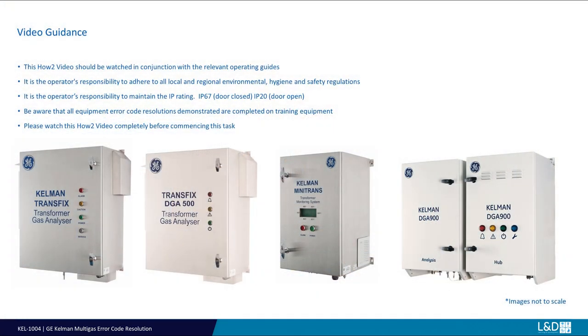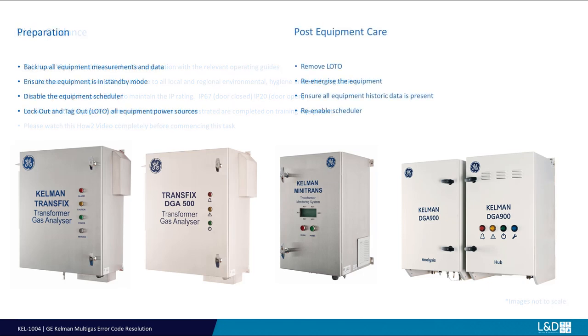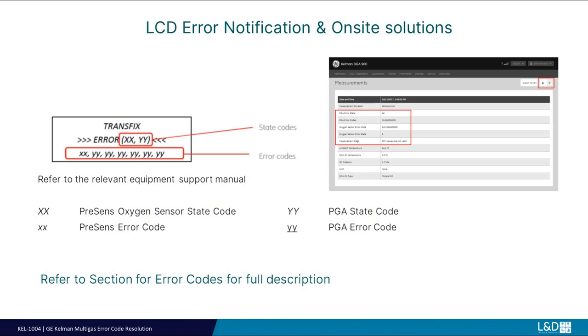For all monitors operating in varying environmental conditions and at all times of day, a proactive equipment care programme can reduce or prevent most system operation error alarms. If your Kelman Multigas Monitor identifies a problem with the active measurement cycle, by design it will abort the measurement and provide the operator with a system error code or message highlighting the potential problem with the monitor and or setup.